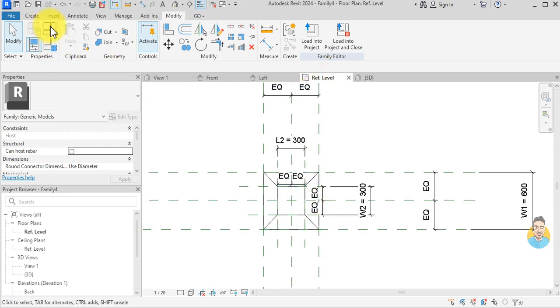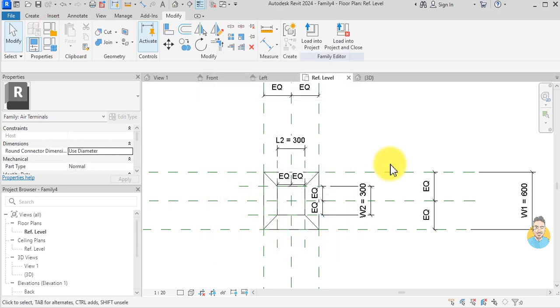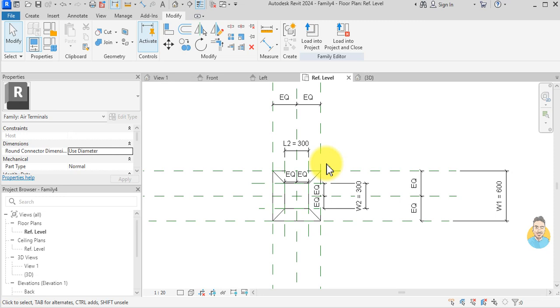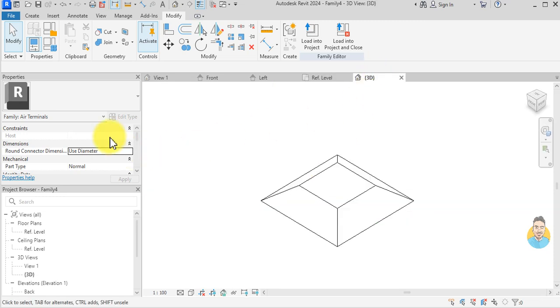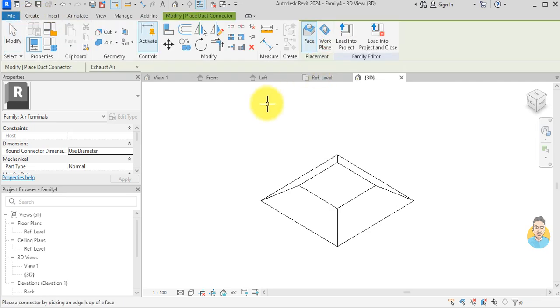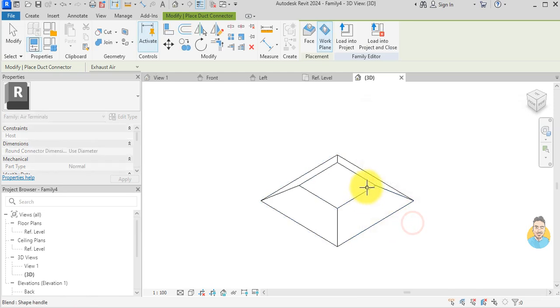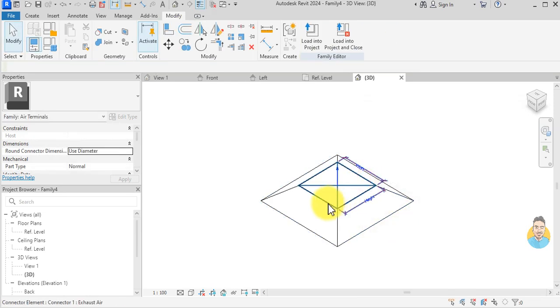Next I go to Family Categories and give it the Air Terminal category, then click OK. I want to add a connector — go to the 3D view, Create Duct Connector, then Work Plane, pick a plane, and this is my duct connector.